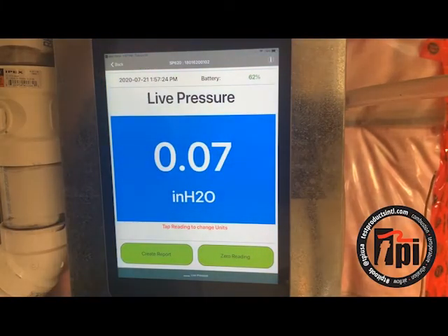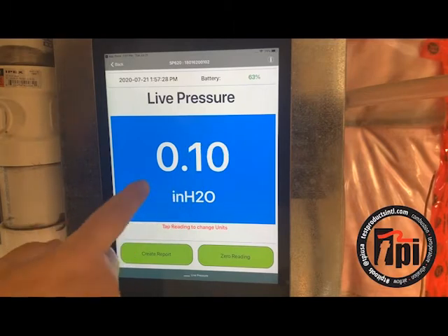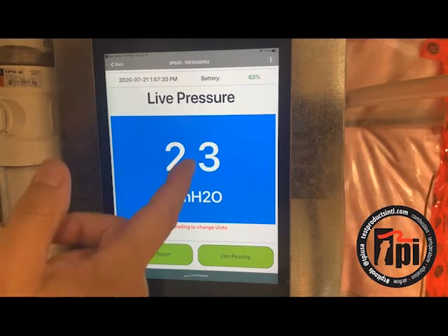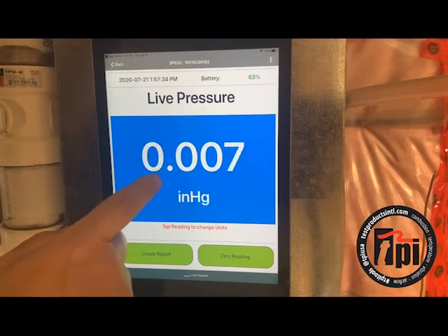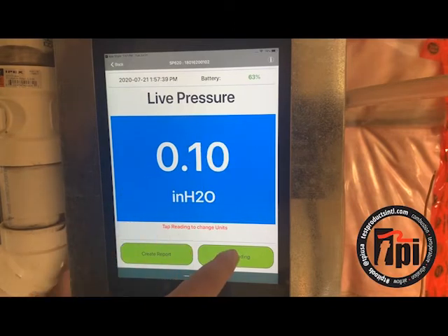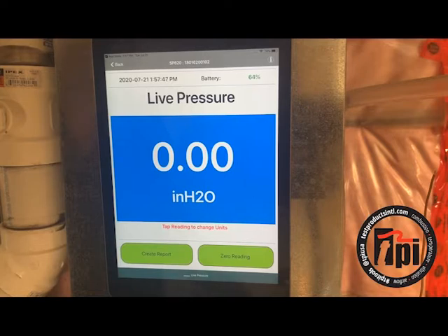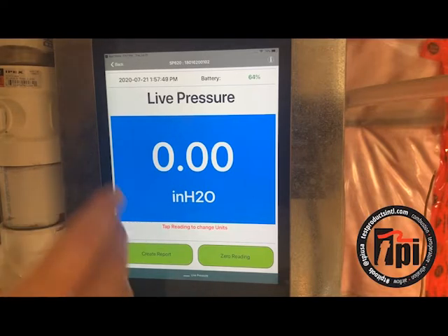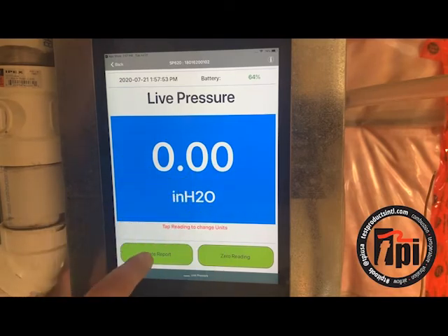It's communicating with it. If I want to change my units of measure — right now I have it in inches — I just tap on it and it goes to millimeters, KPA, and so forth. I'm going to go back to inches of water column, and I can zero my reading. Right now I'm in front of a two-stage furnace, so if I want to set my low fire and high fire, I hook up my manometer, get the right reading I'm looking for, and then I can create a report.